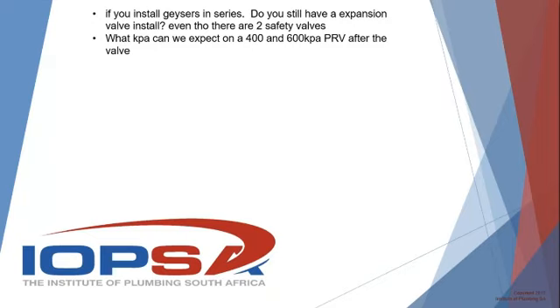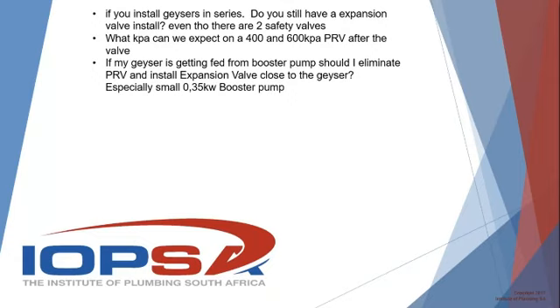Correct. Okay, so what kPa can we expect on a 400 and 600 PRV after the valve? I think you've answered that already, Patrick. Yes, it's on any valve, it's a percentage. So you're looking at between 75 and 80% of the rating of the valve. On a 400 kPa, it's between 280 and 340, and on a 600 kPa, you're looking at about 450 kPa, somewhere around there.